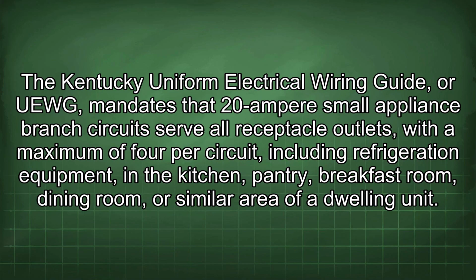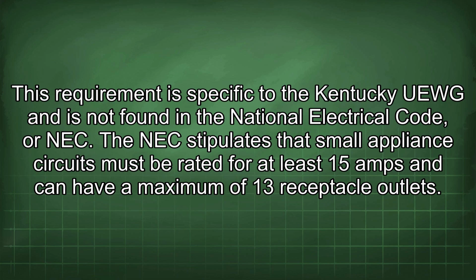The Kentucky Uniform Electrical Wiring Guide, or UEWG, mandates that 20 ampere small appliance branch circuits serve all receptacle outlets, with a maximum of 4 per circuit, including refrigeration equipment, in the kitchen, pantry, breakfast room, dining room, or similar area of a dwelling unit. This requirement is specific to the Kentucky UEWG and is not found in the National Electrical Code, or NEC.